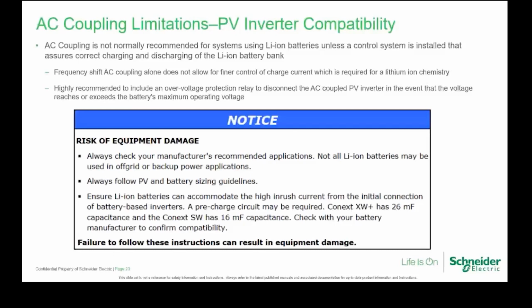We also highly recommend including an overvoltage protection relay to disconnect the AC coupled PV inverter in the event that the voltage reaches or exceeds the battery maximum operating voltage. So it's just a bit of a backup. Check the manufacturer's recommended applications, follow the PV and battery sizing guidelines, and make sure the lithium battery can accommodate the high inrush current from the initial connection of the battery-based inverters. A pre-charge circuit might also be required, so check with your battery manufacturer first.